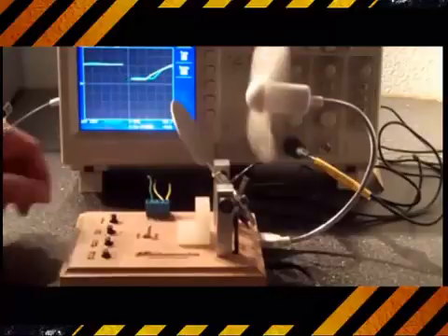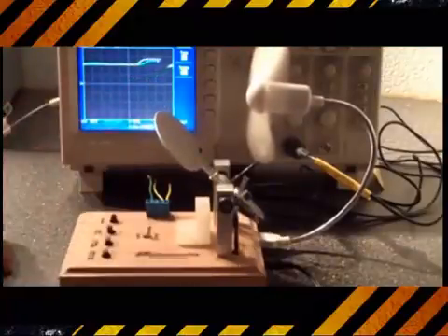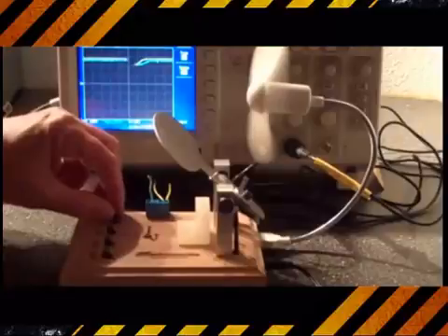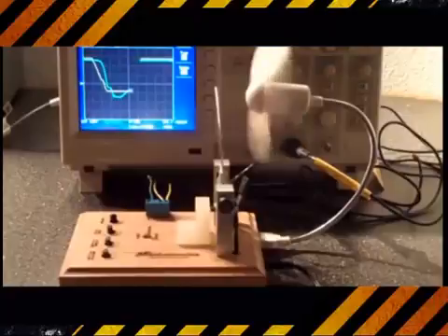And the important point to note is that the bigger the integral action, the quicker it will get to this 20% value. That is, it will take fewer minutes to get there. So the minutes per repeat value will be smaller. In other words, the smaller the minutes per repeat, the bigger the integral action. To make things a bit more intuitive, a lot of controllers use an alternative unit of repeats per minute, which is obviously the inverse of minutes per repeat. The nice thing about repeats per minute is that the bigger it is, the bigger the resulting integral action is.